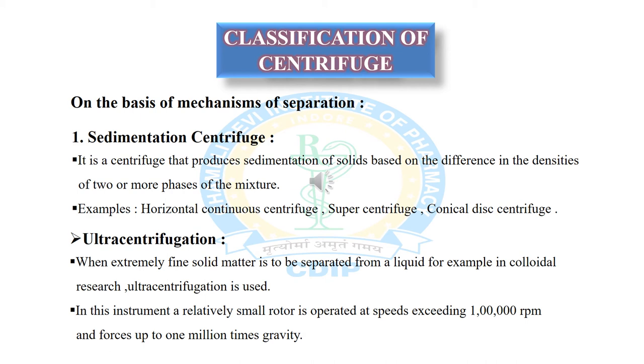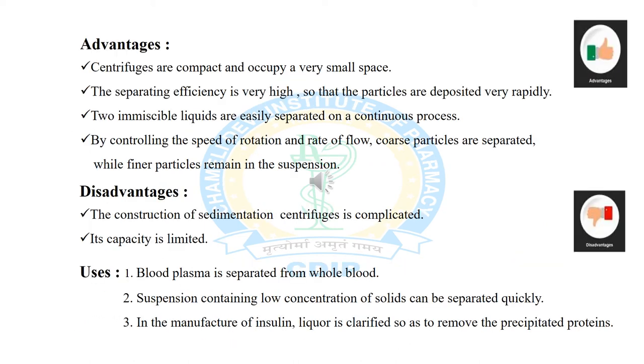Ultracentrifugation is based on the sedimentation type of centrifuge. When extremely fine solid matter is to be separated from a liquid — for example in colloid research — ultracentrifugation is used. In this instrument, a relatively small rotor is operated at a speed exceeding one lakh rpm and forces up to one million times gravity.